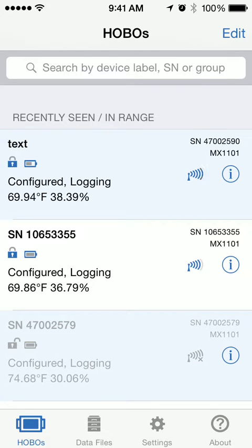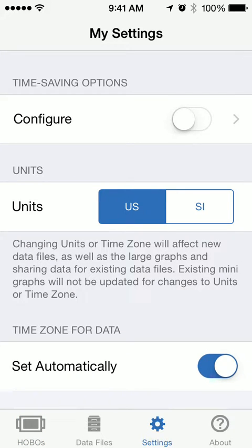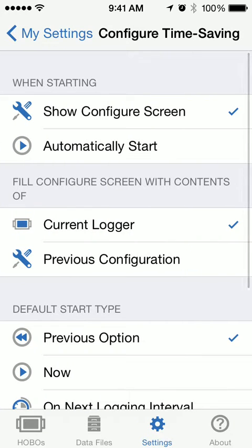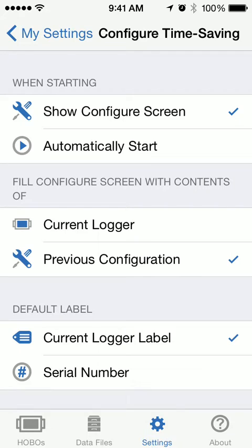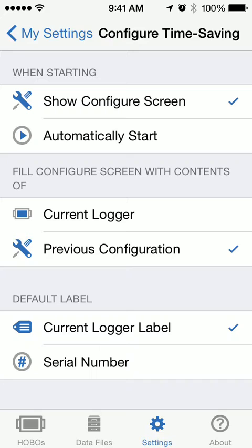In Hobo Mobile 1.1 we've added a time-saving feature for configure and start. To access it, tap on Settings, then the very top option: Time-Saving Options. Turn on Configure and tap it to bring it over to settings. When you go to start your logger, you can either show the configuration or have it start automatically. You can fill the screen contents from the current logger or the previous configuration, and set the default label to the current logger or the serial number.